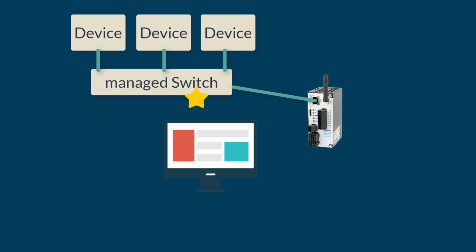If it's needed to record an event, for example during the boot up, the built-in sniffer tool can't be used. In this case, it might be necessary to install, for example, the tool Wireshark on your computer, connecting it to the port mirroring port of the network switch, and perform the trace outside the gateway. This can also be useful for debugging Profinet or Ethernet IP traffic, since they are not connected to the internal tracing tool.